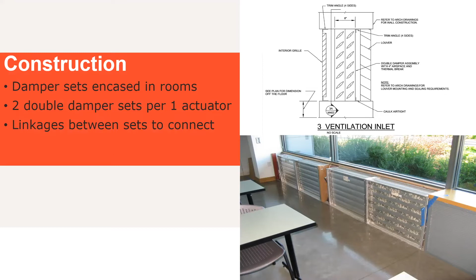Here is the double damper set. Two dampers stacked deep, I think they were closed, closing parallel wise, in opposite directions. So not opposed blade dampers, but parallel dampers inversed. They were encased in a box with a big grill in the front and casework on top, so access was an issue. There's only one actuator per double set, so for a quadruple arrangement, two deep and two wide, you have one actuator and linkages. Does anybody smell a problem with that?